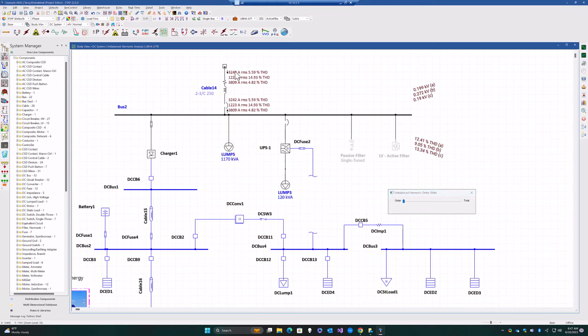And what you can see reported here is phase A, phase B, and phase C, which are quite substantially unbalanced, which I did on purpose. And you can, of course, see that the distortion on each phase is quite substantially different. When you run a balanced harmonic analysis and compare with the assessment standards, they don't take this kind of unbalance into account. We're always looking at average values, and it's very easy to miss out on the fact that one of the phase unbalances can cause a very serious detrimental effect on your current harmonic distortion.